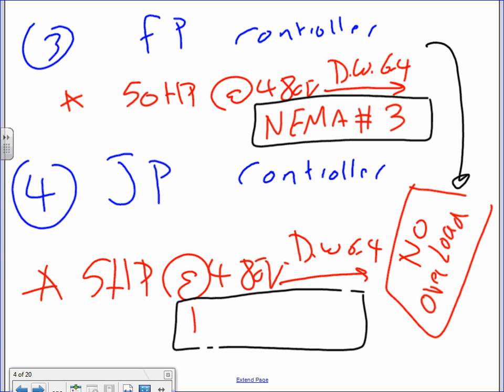NEMA number 3. Both of them, Matt, both of them shall not have an overload. Guys, fire pumps are required not to have an overload like other motors. The reason: if you have a fire in your building and your fire pump is running, do you care about overloading the fire pump when half of your building is on fire? Is that a concern to you?